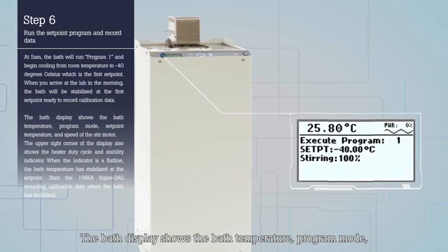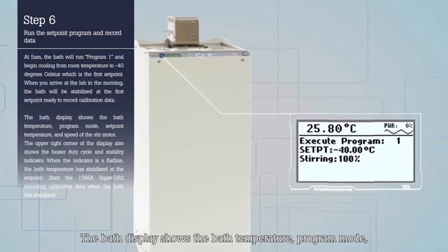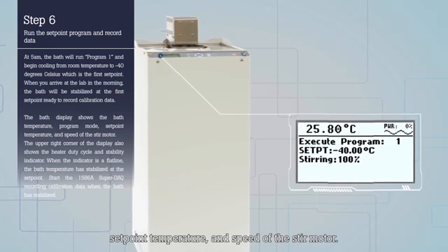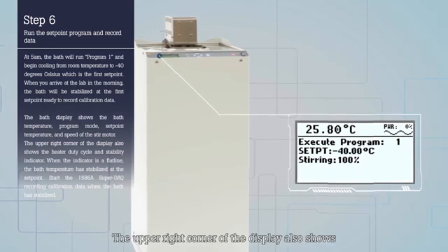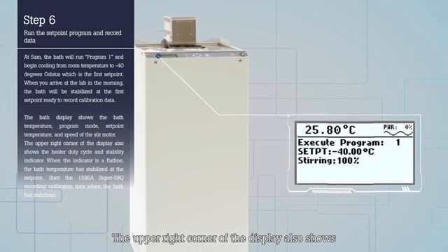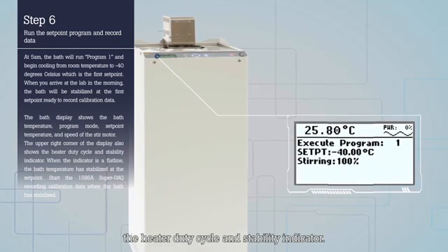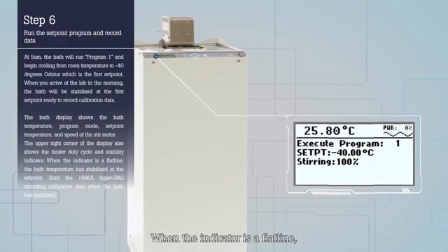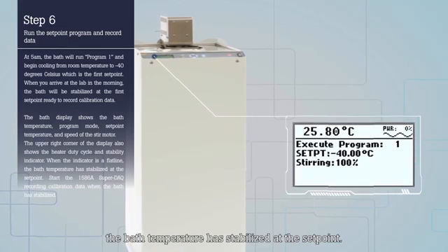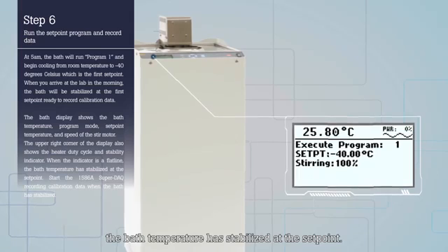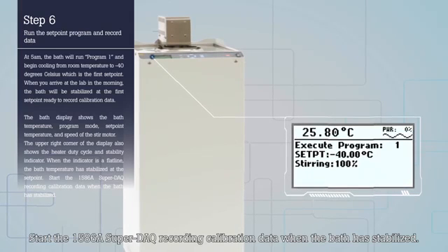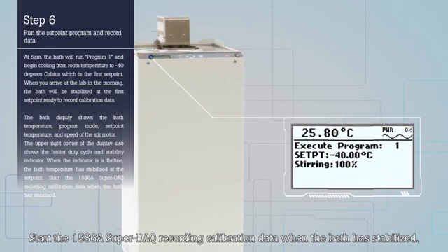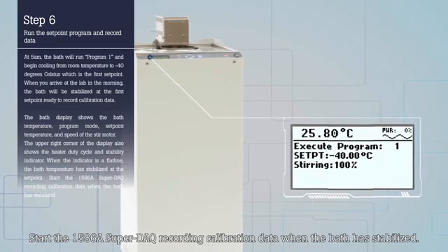The bath display shows the bath temperature, program mode, set point temperature and speed of the stir motor. The upper right corner of the display also shows the heater duty cycle and stability indicator. When the indicator is a flat line, the bath temperature has stabilized at the set point. Start the 1586A Super-DAQ recording calibration data when the bath has stabilized.